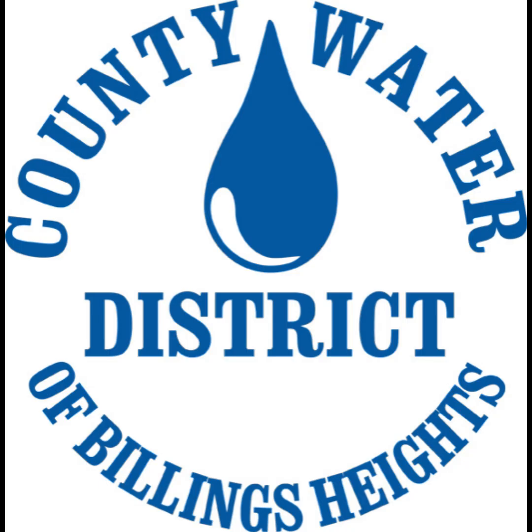So I put a suggested path forward. Again, take it for what it is. It's up to you. I just want you guys to have the information. So just to summarize, using the industry standards to estimate design flows, I just recommend getting a second opinion on the water model's design assumptions to ensure industry standards are utilized in estimating design flows. It suggests more fully understanding, you guys are already asking these questions, your operator's preference to eliminate the use of booster stations, because continued use of booster stations can result in considerably less cost.